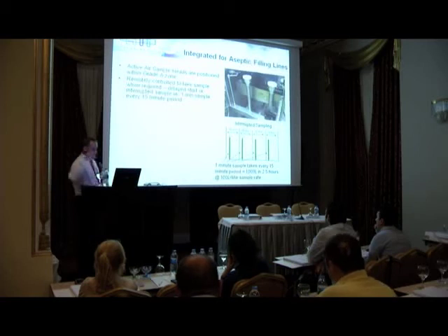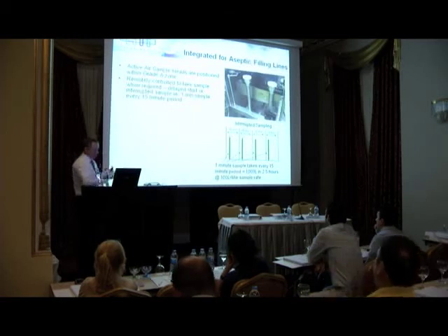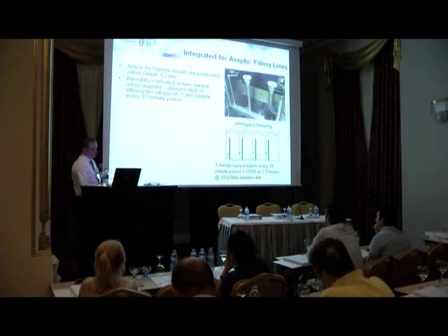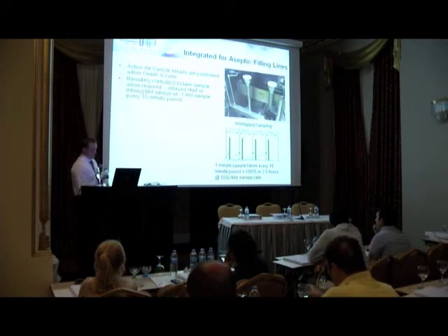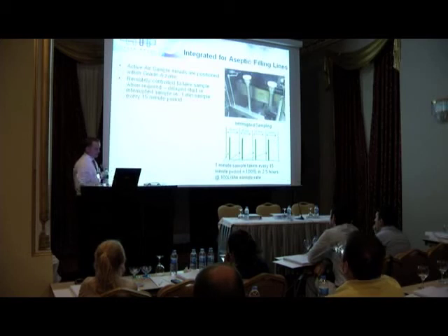So the idea of this is, if your production run is going to take, say, 2 hours, you start this running 15 minutes before, start production, and then complete production, and you've proven that you've had no viable counts before production, during production, and after production. So it stops you having to make interventions and putting in different agar runs, basically.